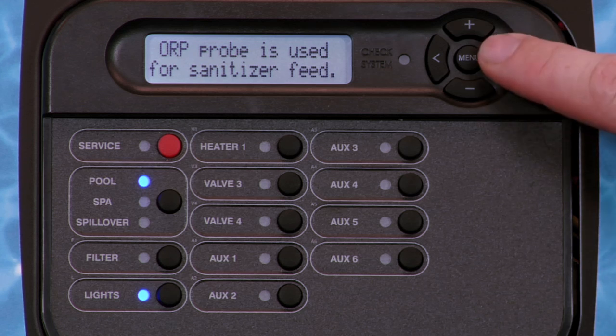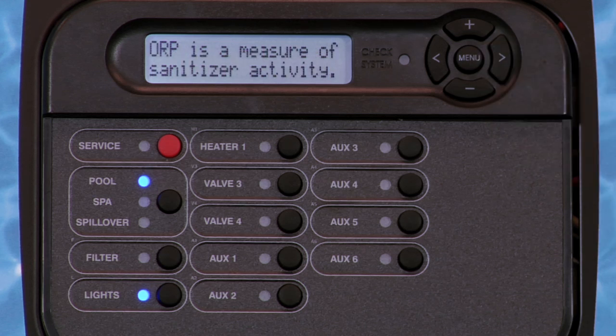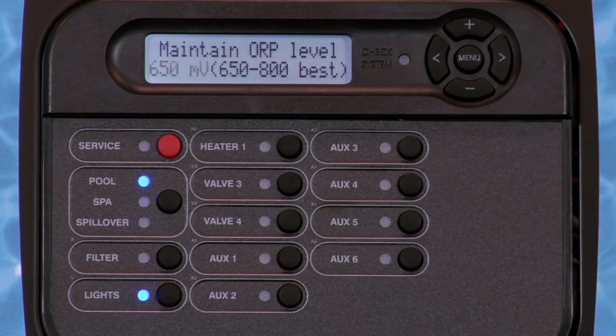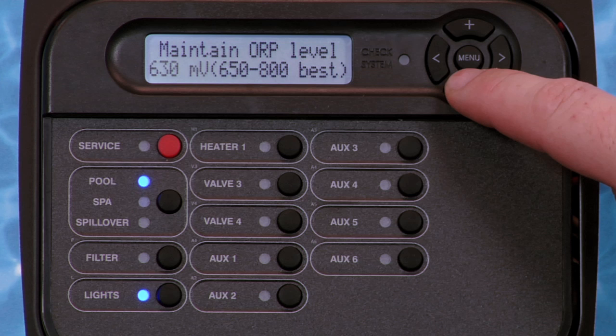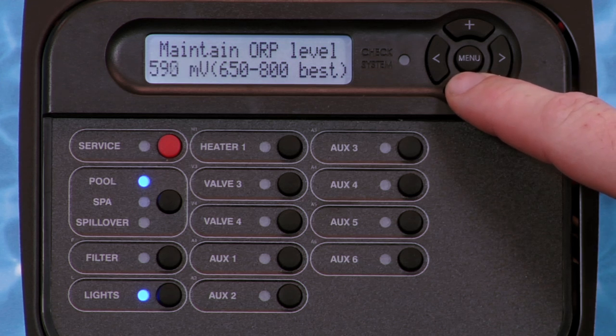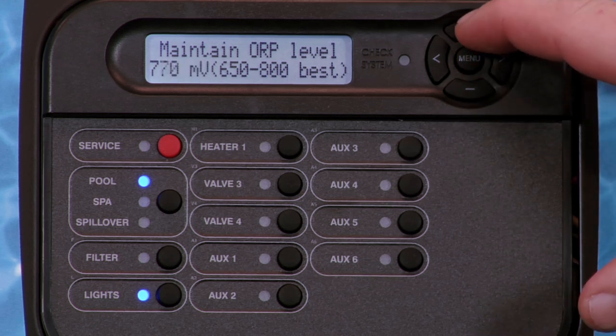Press the right arrow key three times to move through the next two screens, where the chemistry wizard explains the function of ORP. The Maintain ORP Level screen is where you can adjust the ideal level of ORP for Sense and Dispense. Although 650 to 800 millivolts is the factory default and preferred level, you can press the plus or minus key to adjust the ORP range. The minimum value is 400 millivolts, and the maximum value is 900 millivolts.